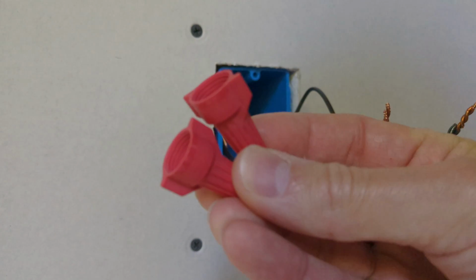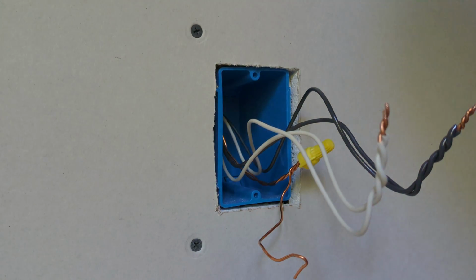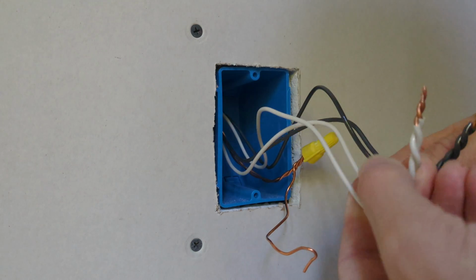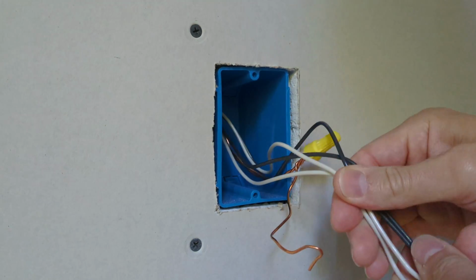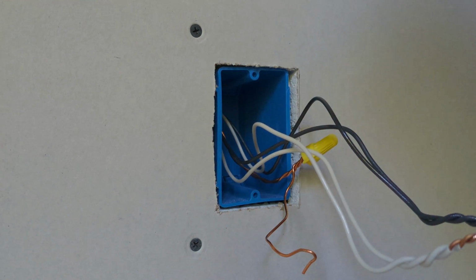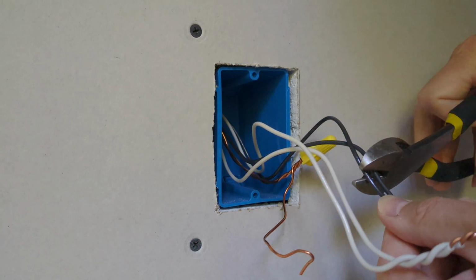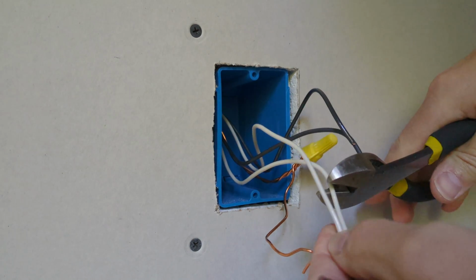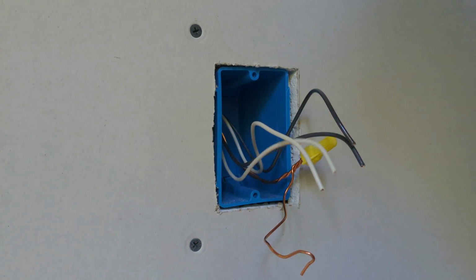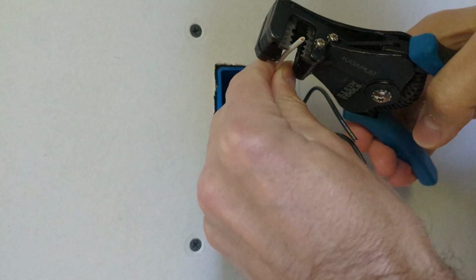These red wire nuts, I'm going to reuse those. The box says those are good for 2 to 6 number 14 wires. So I'll have 3, that's fine. I've got a little bit extra length here that I don't need, so I'm gonna cut a little bit of that off. I'll strip these wires.